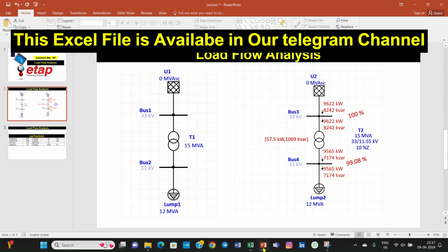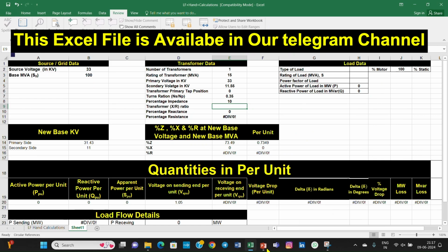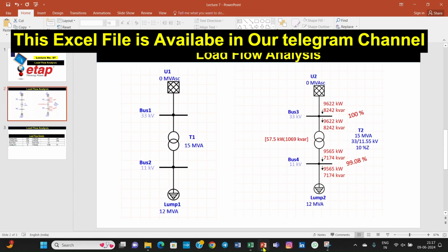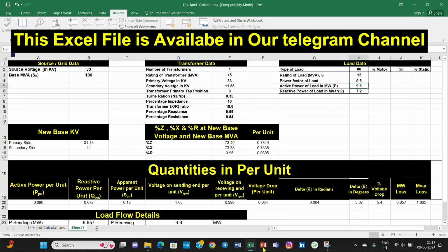The transformer X/R ratio we have taken in the ETAP software is 18.6, so we can enter 18.6 here. You can see most of the quantities have been calculated. The load here is 80% motor load. The same has been taken in ETAP. Rating of load is 12 MVA, and power factor is 0.8. You can see the different parameters are being calculated.